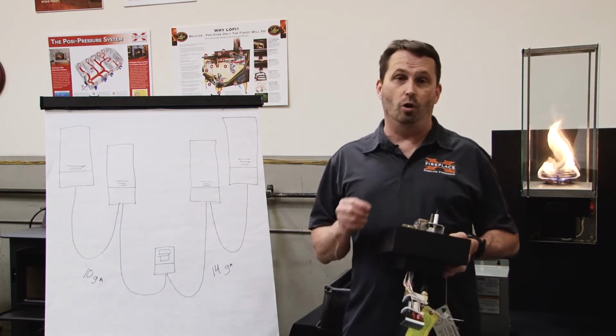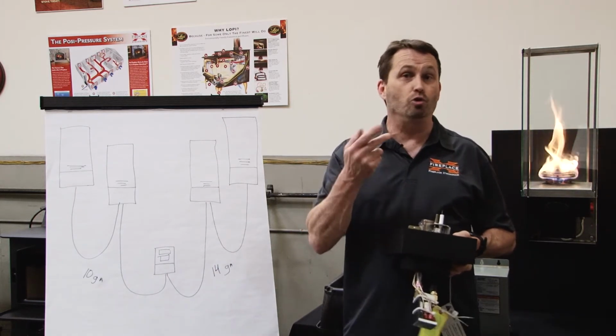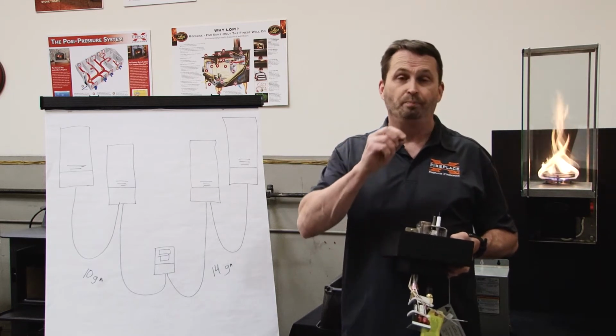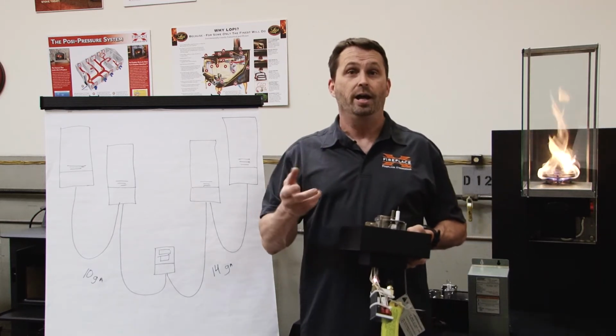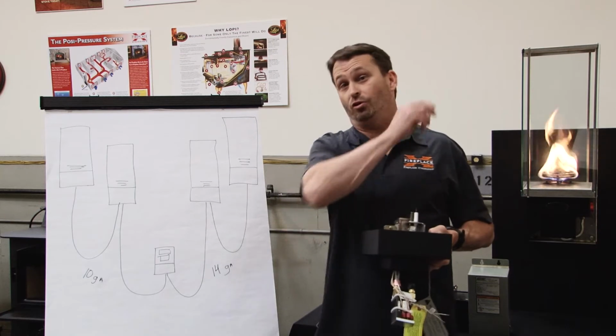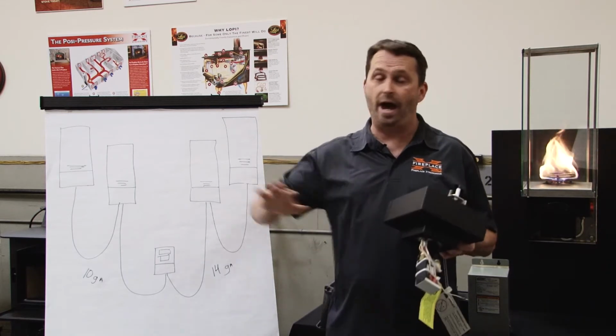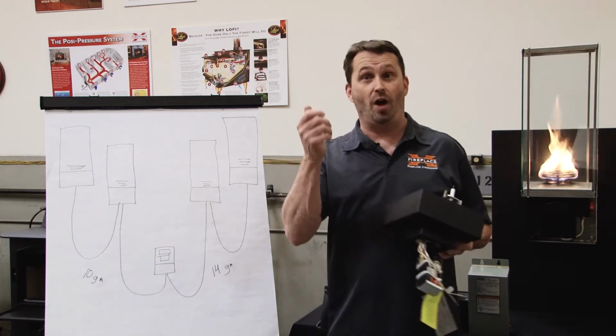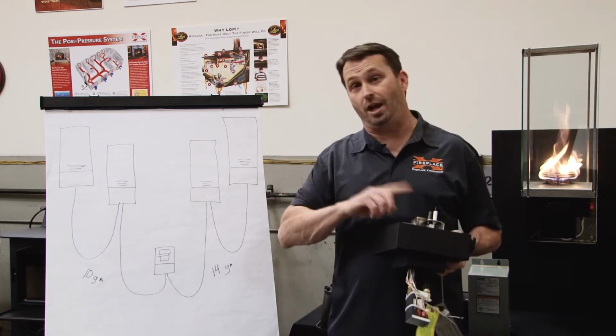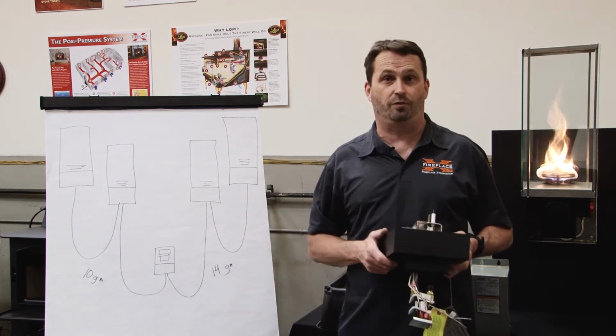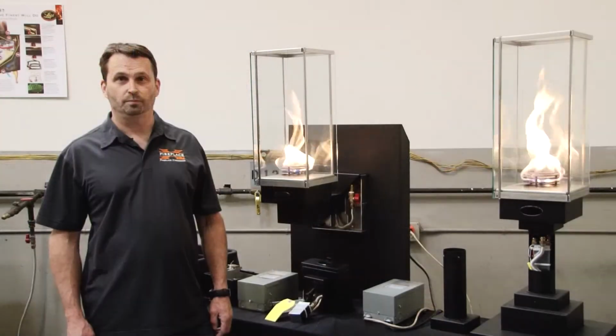Now you'll find on your low voltage wiring, it's a two-strand wire. One of the strands will have writing on it, and the writing will be continuous from one side to the other. So if you have 400 feet of wire, just find the one with the writing on it, and that'll be the same at both ends to just make it easier to tell which is which.